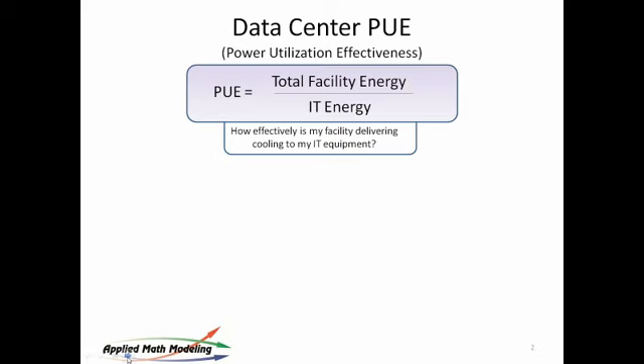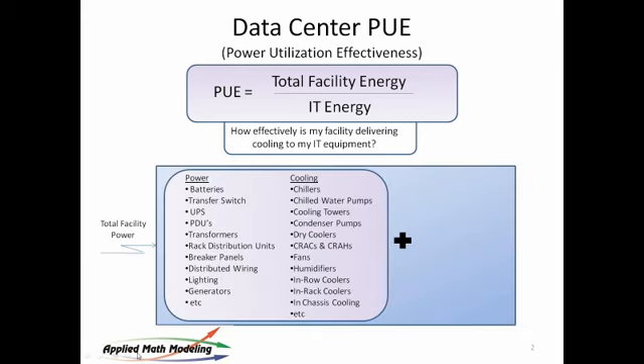So the first one we'll do is PUE. PUE is total facility energy divided by IT energy. And it's really a measure of how effectively the data center is delivering cooling to the IT equipment itself. The total facility power is made up of the IT equipment plus everything else that takes energy, such things as batteries and PDUs and transformers, and of course the cooling system.